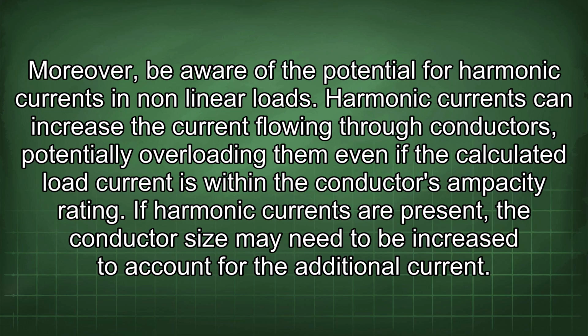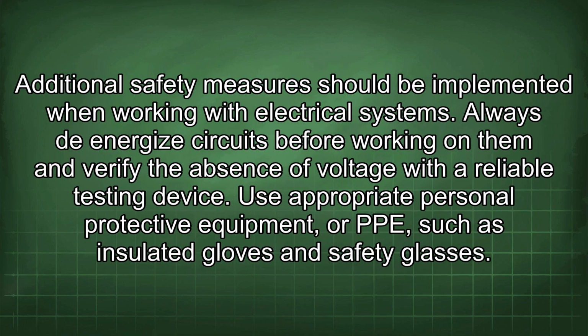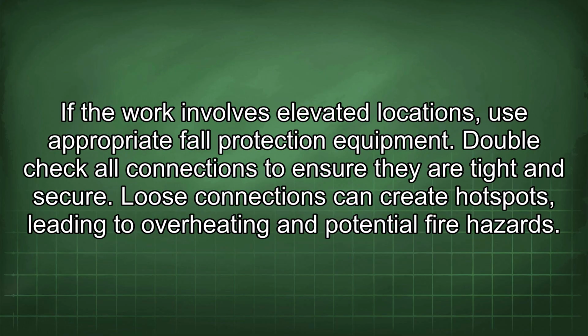If harmonic currents are present, the conductor size may need to be increased to account for the additional current. Additional safety measures should be implemented when working with electrical systems. Always de-energize circuits before working on them and verify the absence of voltage with a reliable testing device. Use appropriate personal protective equipment, or PPE, such as insulated gloves and safety glasses. If the work involves elevated locations, use appropriate fall protection equipment. Double-check all connections to ensure they are tight and secure. Loose connections can create hotspots, leading to overheating and potential fire hazards.